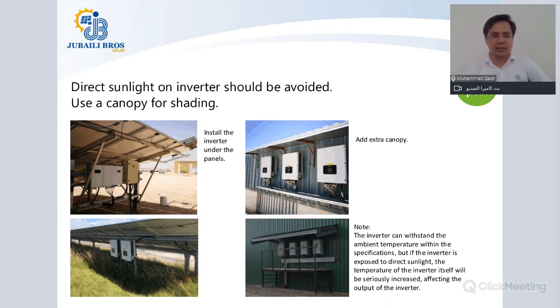Direct sunlight on the inverter should be avoided. Use a canopy for shading. Now, in most scenarios for C&I, the inverters are installed outdoors. In case of a ground mount, you are recommended to install your solar inverters at the backside of your solar frame, underneath the solar panels, which provides very good shading and ventilation.